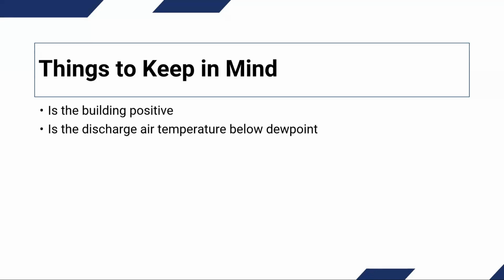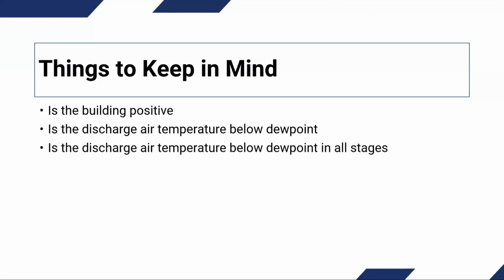We have a lot of projects where they want the discharge air temperature to reset for energy savings, and that's fine. We have no problem with that. But we always try to make sure that whatever that reset is, we're never risking the chance that discharge air temperature is going to be above the dew point, to where we can't remove the moisture. Another key factor is, is it reaching dew point at all stages?